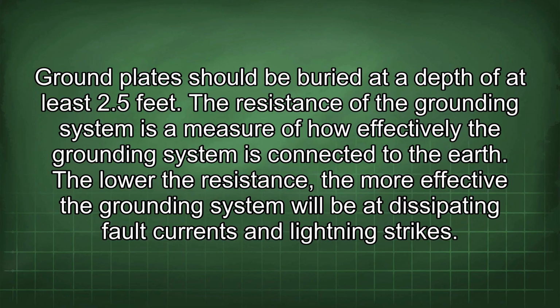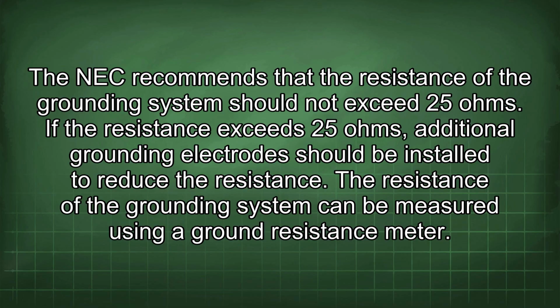The resistance of the grounding system is a measure of how effectively the grounding system is connected to the earth. The lower the resistance, the more effective the grounding system will be at dissipating fault currents and lightning strikes. The NEC recommends that the resistance of the grounding system should not exceed 25 ohms. If the resistance exceeds 25 ohms, additional grounding electrodes should be installed to reduce the resistance.